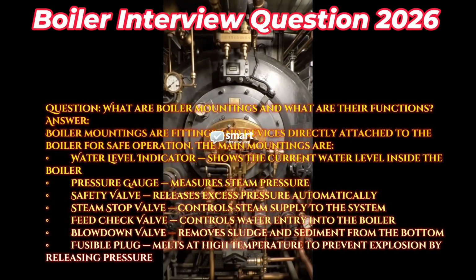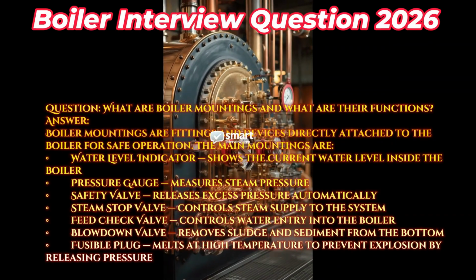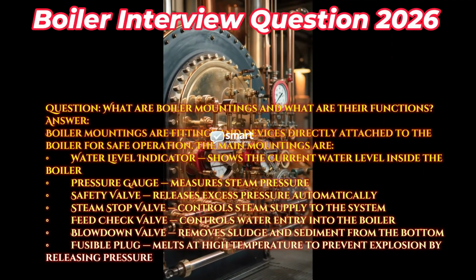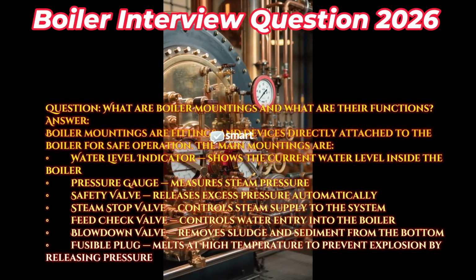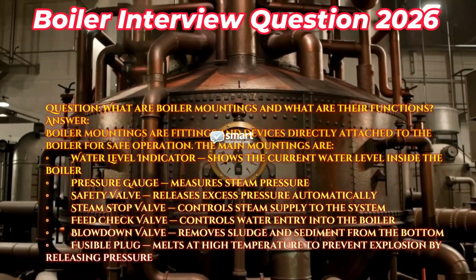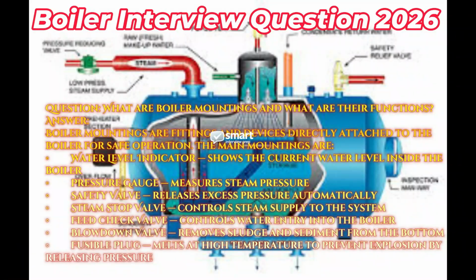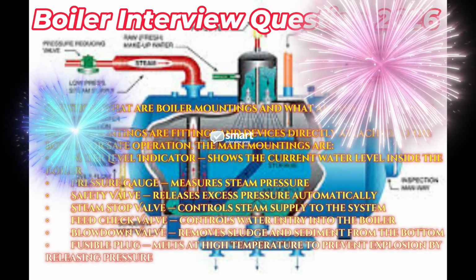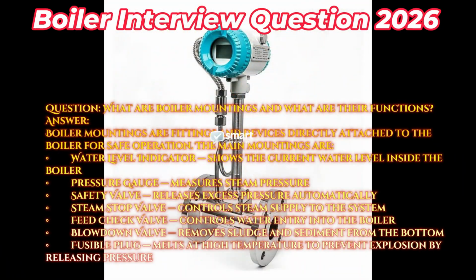The steam stop valve controls steam supply to the system. Feed check valve controls water entry into the boiler. Blowdown valve removes sludge and sediment from the bottom. Fusible plug melts at high temperature to prevent explosion by releasing pressure.